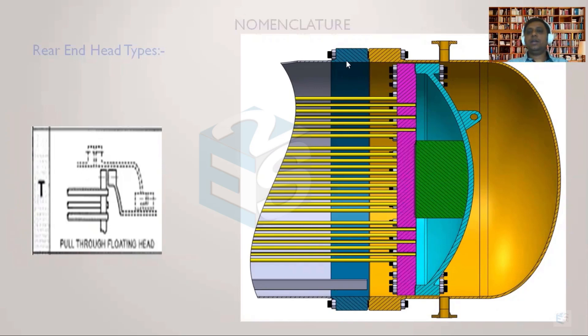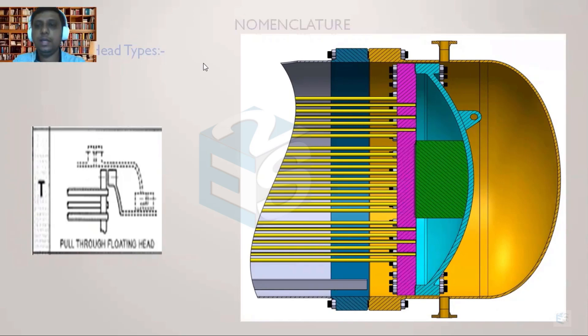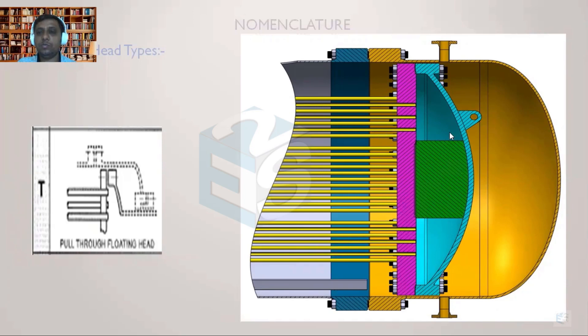More sealing strips need to be provided to increase heat transfer. The T-type construction is very simple compared to the S-type because there is no split ring. There is a tube sheet attached to the tubes and a floating head — both have flange construction so they are easily tightened against each other with a gasket. Whenever there is high temperature or high pressure, this entire assembly floats or moves toward the right, and when temperature drops it regains its original position. There is a gap between the tube sheet OD and the shell ID, so there is no interconnection, allowing free expansion and preventing thermal stresses caused by interlocking of the shell side and tube side.